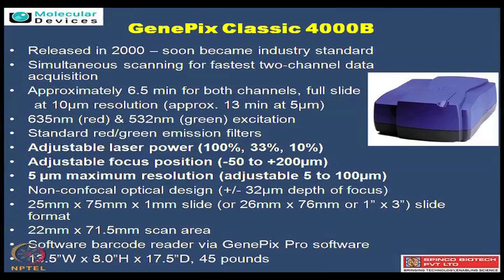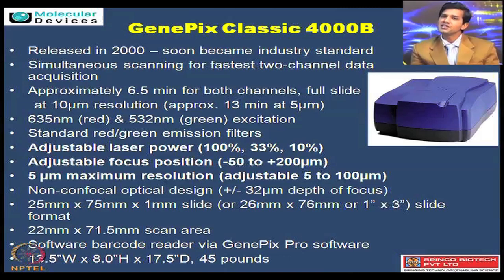GenePix classic 4000B has 6.5 minutes of simultaneous scan - meaning both lasers scan at the same time, so you have very little time for scanning. Apart from that it has two lasers - 635 and 532 nanometers - which are classically used for Cy3 and Cy5 and their own compatible dyes. In view of this, it has standard green and standard red emission filters to accommodate all Cy3 and Cy5 applications.